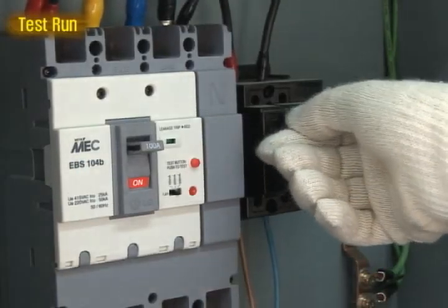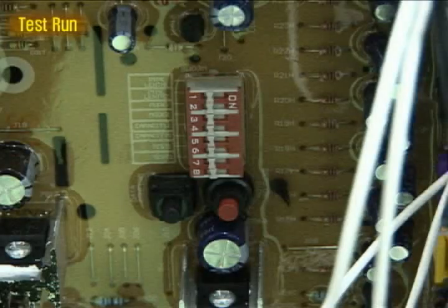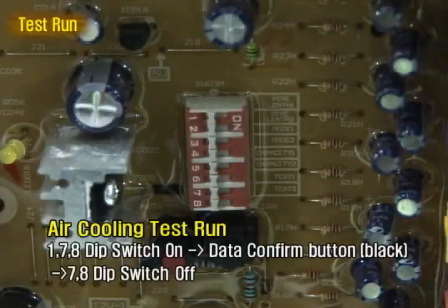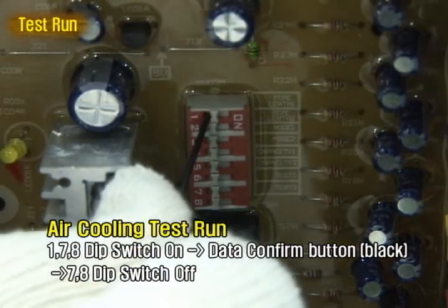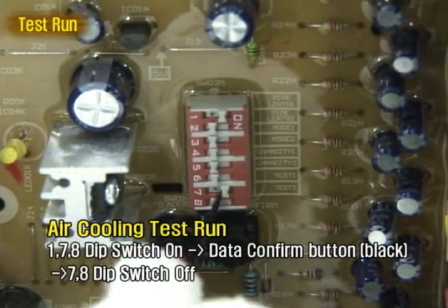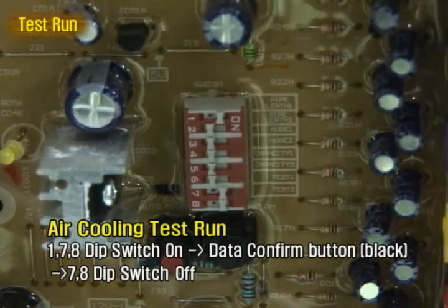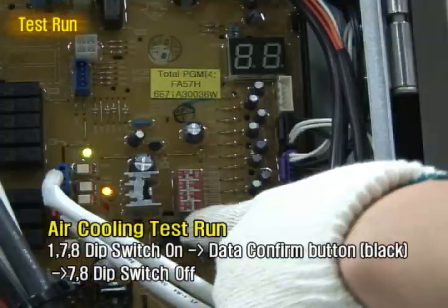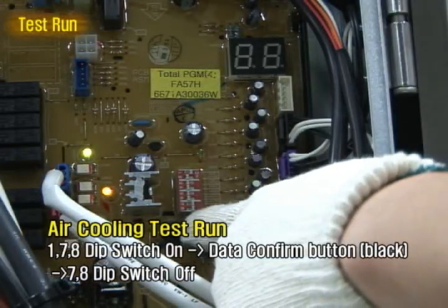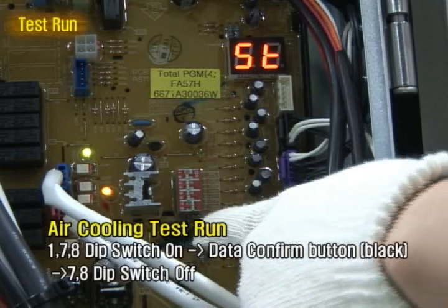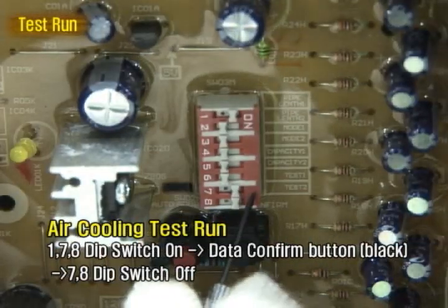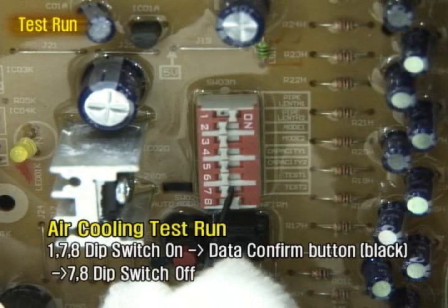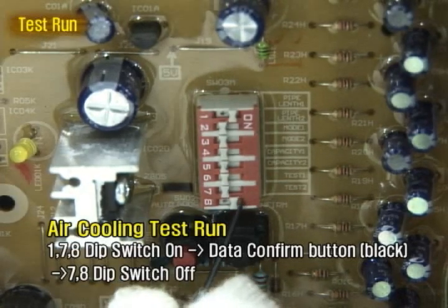At about 1 minute later after the power input, set the dip switch of main outdoor unit like the following. For cooling mode, set the dip switch of 1, 7, and 8 to on, and press data confirm switch. Then ST letter appears on the segment LED. Set the dip switch of 7 and 8 to off to start cooling test run.